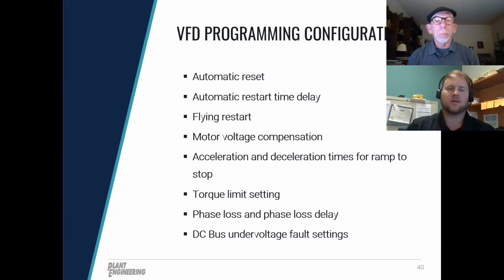A few parameters that I've listed here you're going to want to keep in mind when you're looking at ride-through capability. Automatic restart: how many times will the drive try to restart after a fault? There's going to be a time delay between restart attempts. And then catch on the fly, flying restart. Voltage compensation, so the motor gets enough voltage upon that automatic restart. Also, what is the acceleration time? Is the VFD programmed to ramp to stop, or is it coast to stop? If it's ramp to stop, then what is the deceleration time? Additionally, setting a torque limit so the drive doesn't excessively overload the motor during restart.